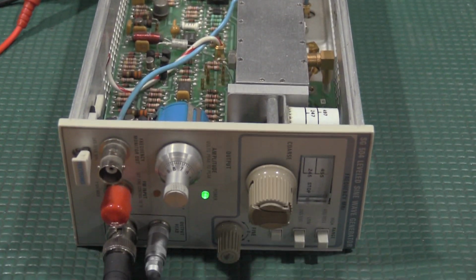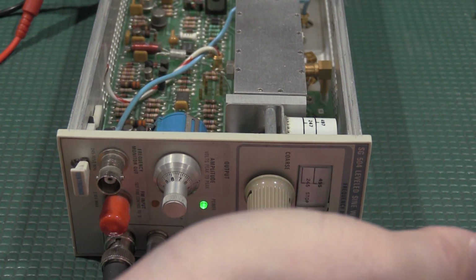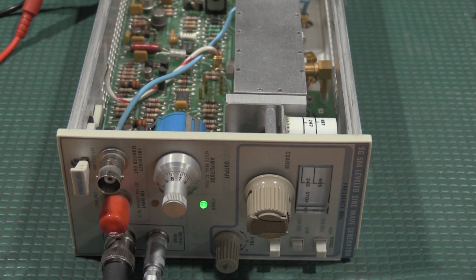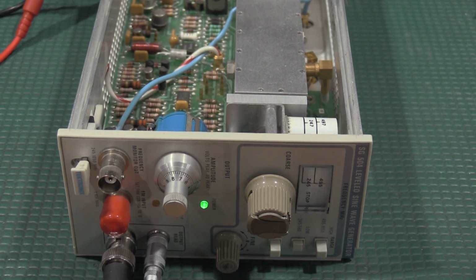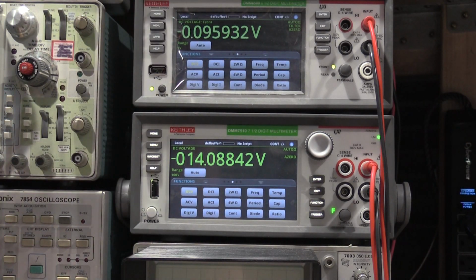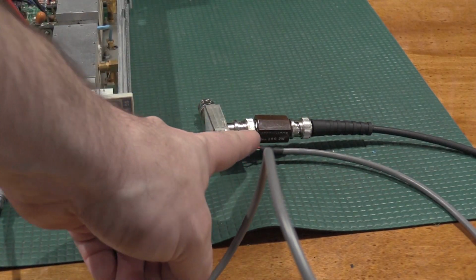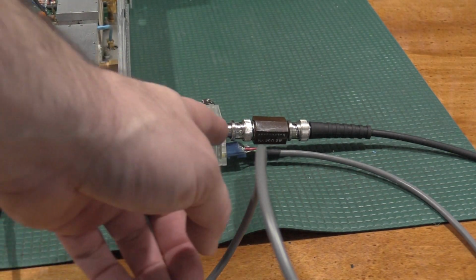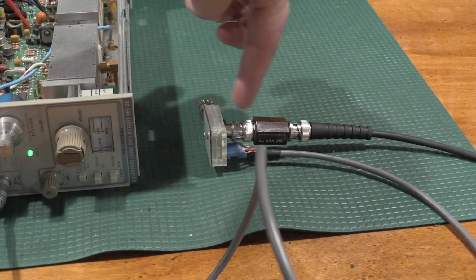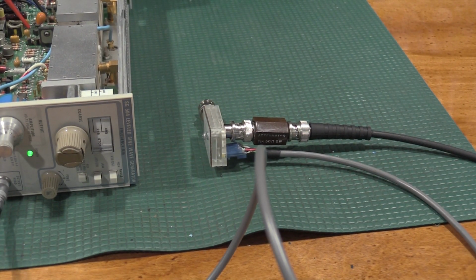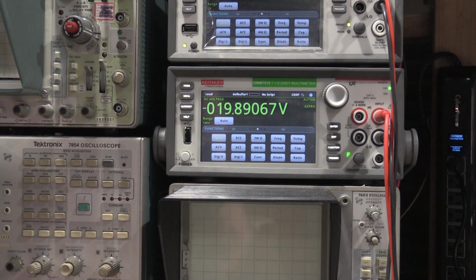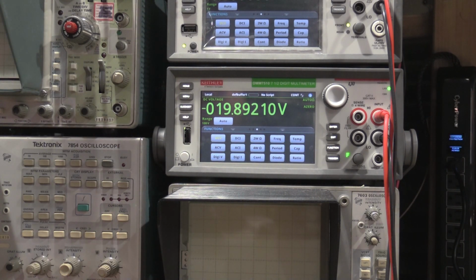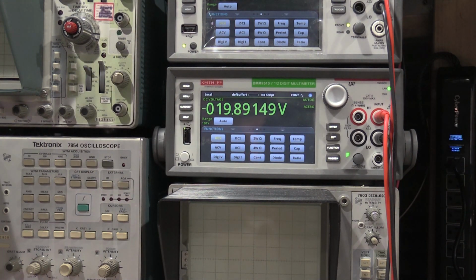And we need to hit the low range. We should have a meter reading of negative 14 volts with plus or minus 400 millivolts. Negative 14 volts, well within spec. Now it wants us to add a 10x attenuator here, which I've done. This is the leveling head, so off the cable coming from the unit to the leveling head, drop it by 10x. Now it's saying we should get approximately 22 to 23.2 volts. I'm a little light there, but it says to record a value that is 1 volt lower than the actual reading, because we'll be needing that in part 8 and 9. So 18.89.